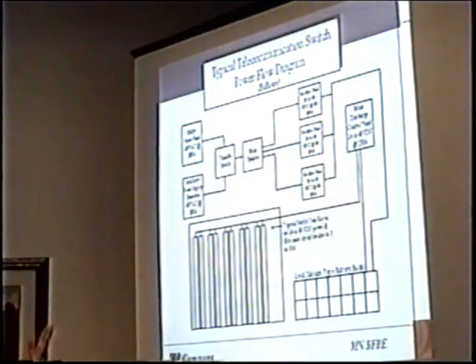This is a flow diagram for a typical telecommunications switch. There are different ways that this can be done, different power supplies, maybe more or less. With computer facilities, you may have different scenarios, but this is not unlike what you would normally have. This came from Bellcore, actually. And you typically have a utility power feed with an auxiliary power supply and a transfer switch. That's a requirement of most any large facility like that. It goes into a main breaker, and then it rectifies down from the AC power coming in to a 24 to 48 volt DC power supply, depending on the scheme that's used for that telecommunications switch.